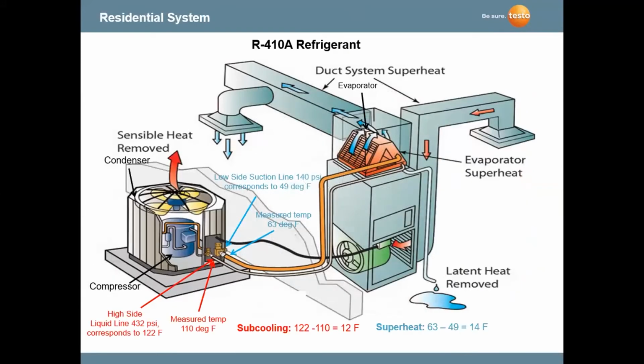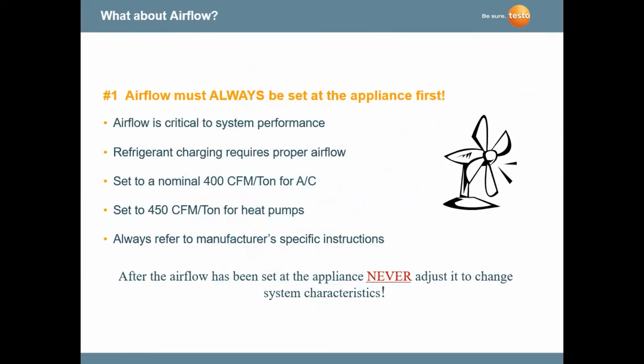So again, we're looking at changes in the equipment. We're going to be talking about superheat and subcooling. We're going to talk a little bit about how we did it in the past and how we do it using a digital gauge. But here's a quick illustration of where the service ports are and where we're taking our primary measurements to get superheat and subcooling. One thing too, before we get into the AC side, is another measurement that we need to do, which is overlooked, and that is airflow.